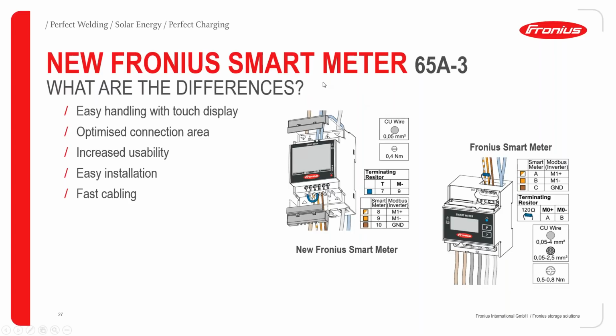Now you come in with the AC in on the upper part of the smart meter, so phases and neutral and protective earth, and the AC out is here at the bottom. That means you go out here again. The communication terminal is below the Fronius ellipse, where you can see the communication ports from 7 to 12, where we connect the Modbus cable with 8, 9, 10: Modbus plus, Modbus minus, and ground. And please do not forget the terminating resistor, which again has to be set between 7 and 9. That's the terminating resistor at the end, the 120 ohms of the communication line.